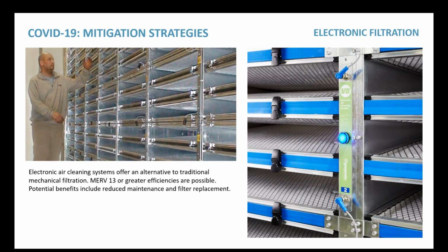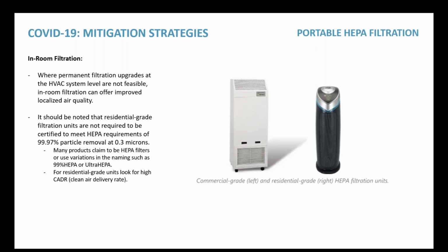And that's important because in existing systems, you may not be able to swap out one filter for the other without having other negative impacts, whether that's impacts on airflow rates or impacts on static pressure. So electronic filtration has been a key recommendation in many cases for existing buildings. There's also portable HEPA filtration. This comes up in a lot of areas, schools to be one, where you're concerned about a lobby maybe would be another. And these are good strategies that can be applied where you're unable to do permanent filtration upgrades at the sort of HVAC system level.